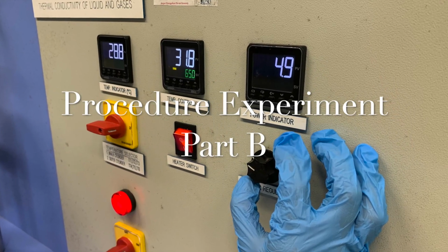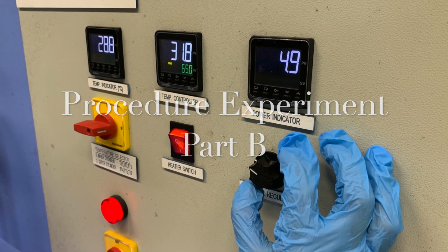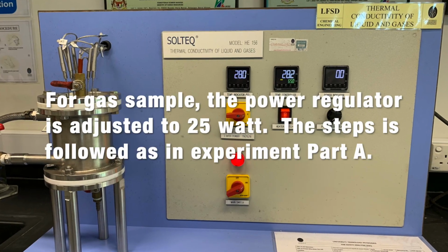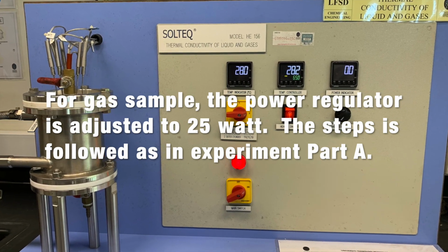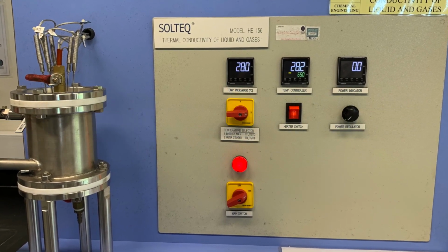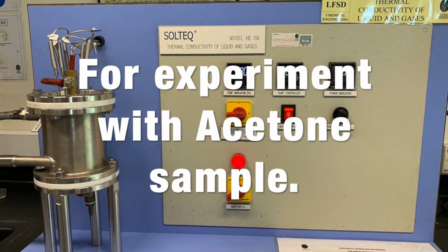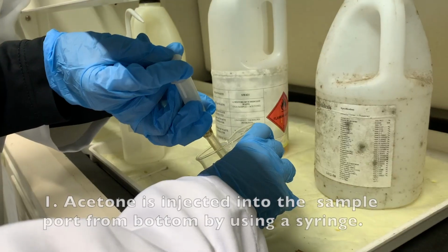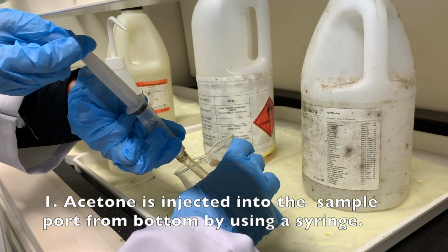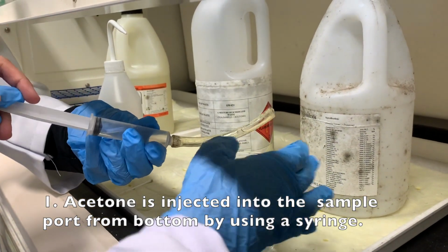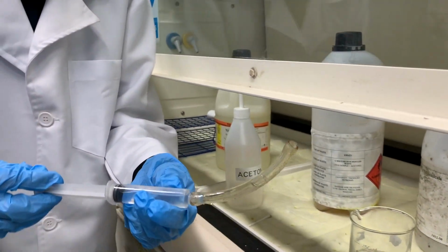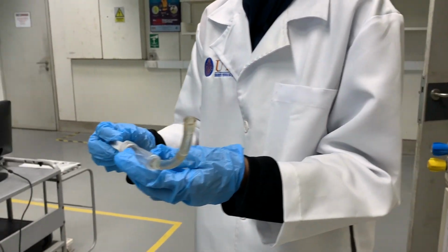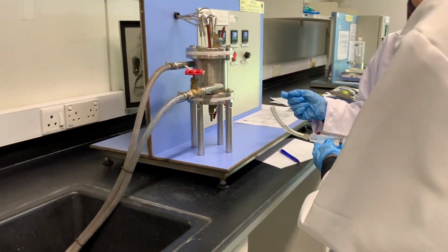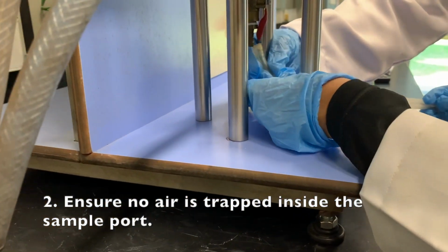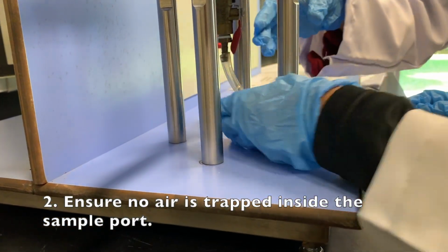Procedure for experiment part B. For the gas sample, the power regulator is adjusted to 25 watt. The steps are followed as in experiment part A. For the experiment with acetone sample, acetone is injected into the sample port from the bottom by using a syringe. Ensure no air is trapped inside the sample port.